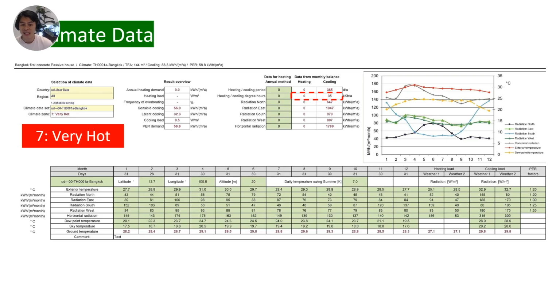In Bangkok climate, there is no need for heating at all. The heating demand is zero. Regarding passive houses in cold climates, building comfort was mostly about keeping people warm in winter. Summer comfort was often ignored, and air conditioning became the easiest solution. But in hot and humid regions like Bangkok, the real challenge is opposite. We don't want heat from the sun or from inside of the building. Our focus is on blocking, delaying, and removing heat so that the indoor temperature stays comfortable. So all of our design strategy here is built around one simple idea: keeping heat out and keeping the inside cool.